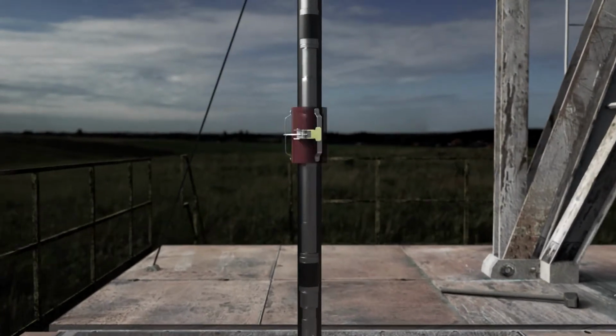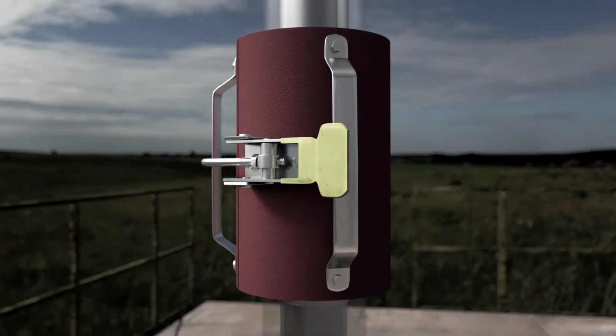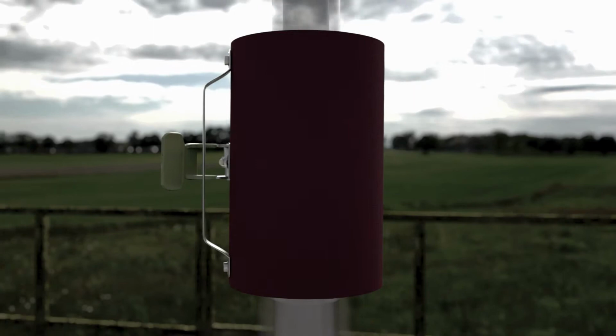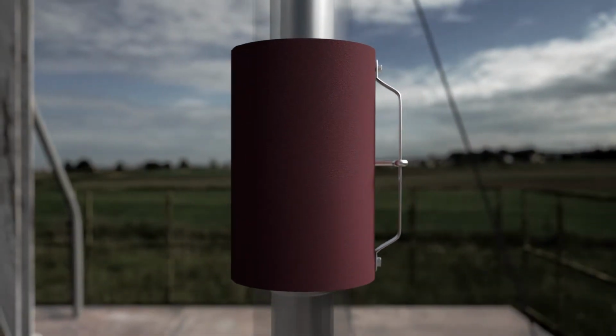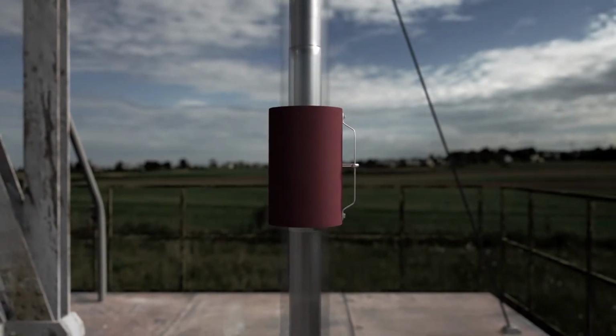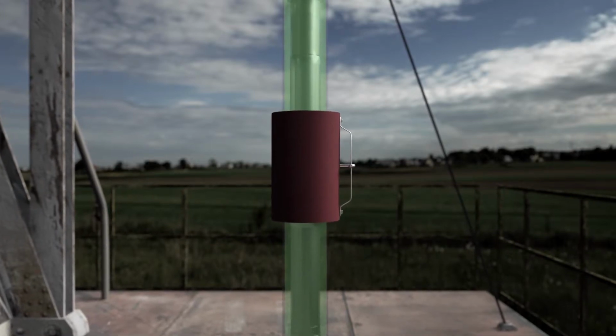After inserting the tool, the leak detection containment sleeve is fitted around the exterior of the pipe connection to capture potential helium leaks. Every containment sleeve is specifically designed for each type of connection and limits the volume of gas for analyzing the concentration of helium. The accumulator then pressures up the tool to the predetermined pressure and sustains it for at least 30 or more seconds based on pipe size and connection.